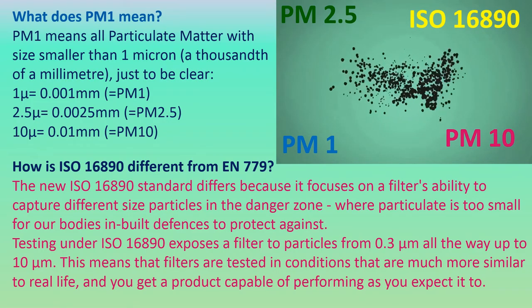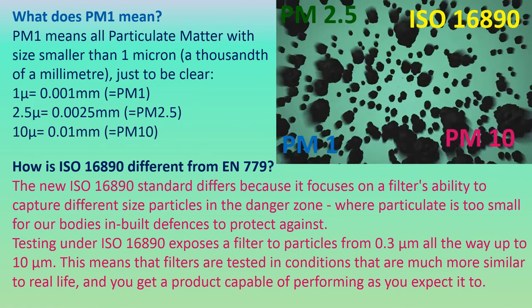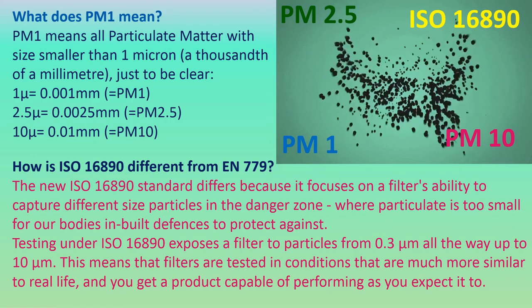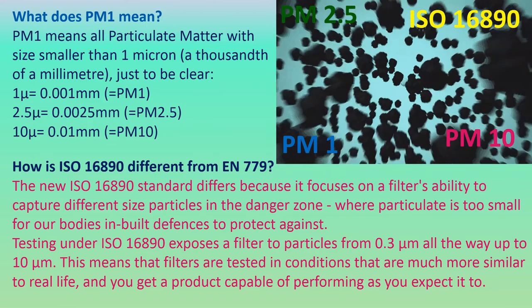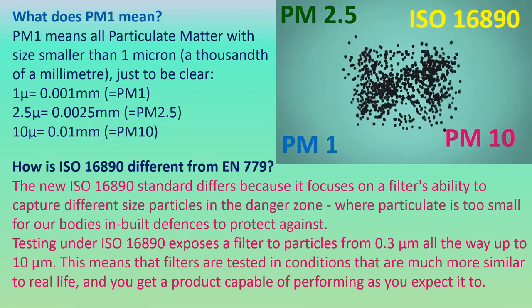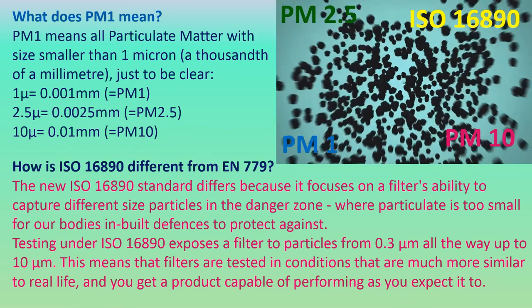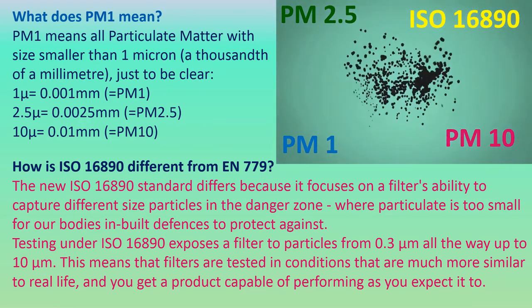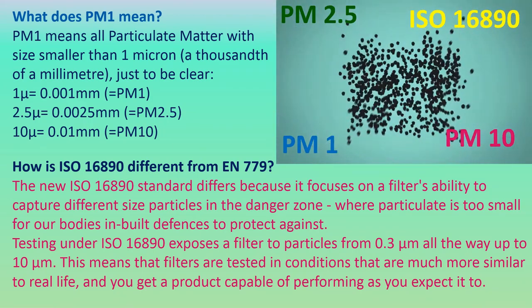How is ISO 16890 different from the EN 779? The new ISO 16890 standard differs because it focuses on a filter's ability to capture different size particles in the danger zone, where particulate is too small for our body's inbuilt defenses to protect against. Testing under ISO 16890 exposes a filter to particles from 0.3 micron all the way up to 10 micron. This means filters are tested in conditions much more similar to real life, and you get a product capable of performing as you expect it to.